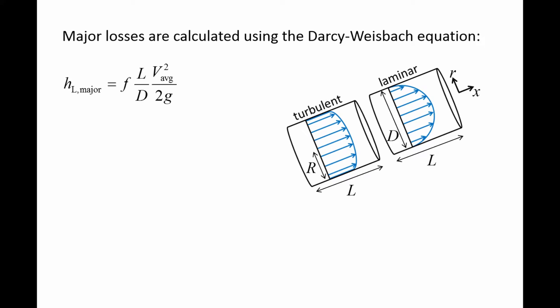In a previous video, we derived an expression for the head loss in a straight pipe of length L and diameter D, which we are now calling the major losses. This expression is called the Darcy-Weisbach equation and states that the major losses are equal to the friction factor f times L over D times V average squared over 2g.